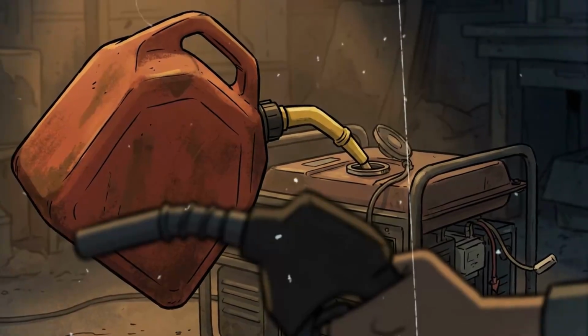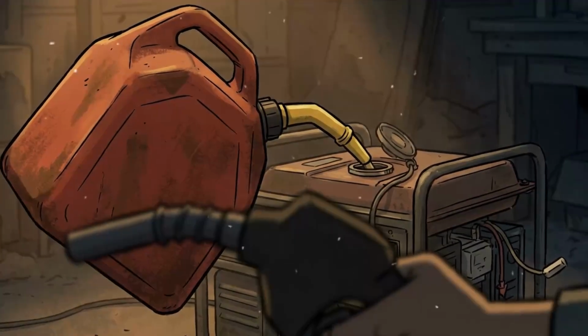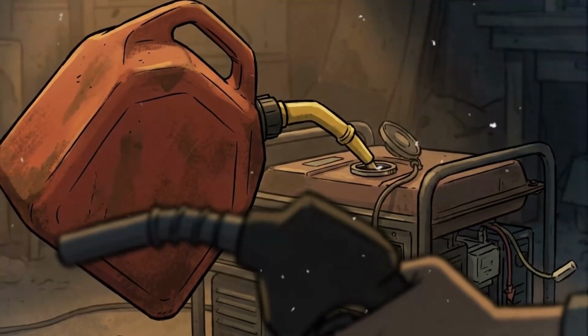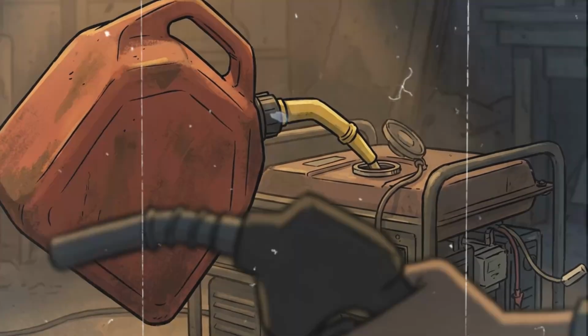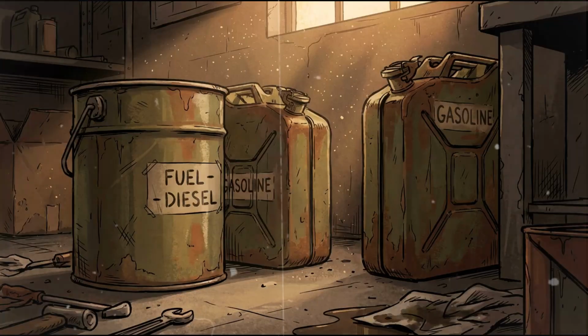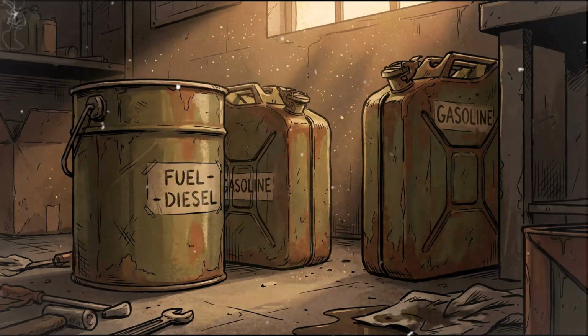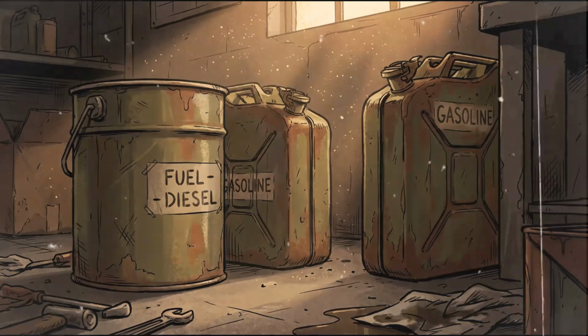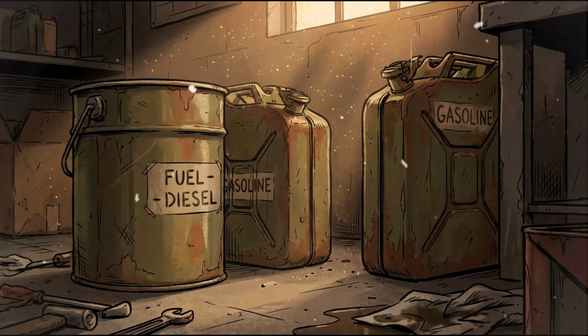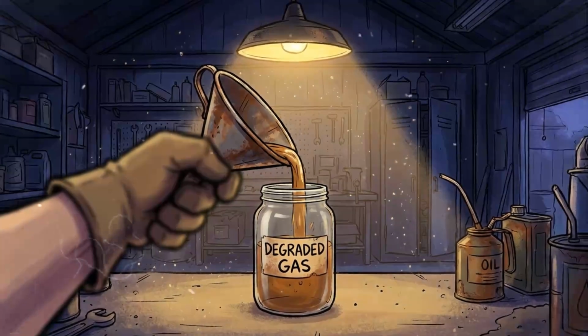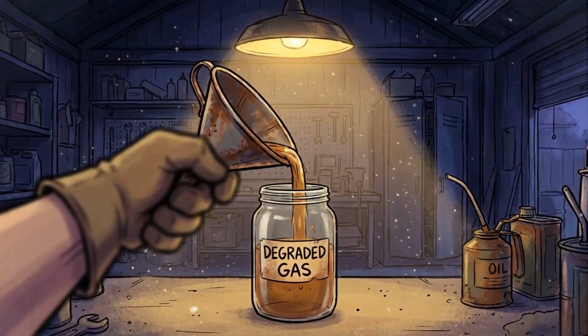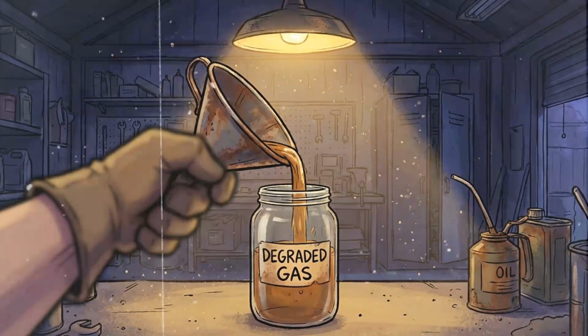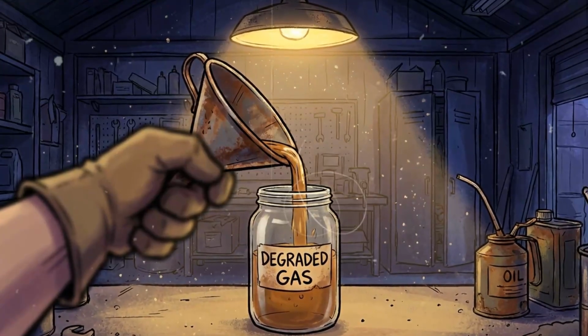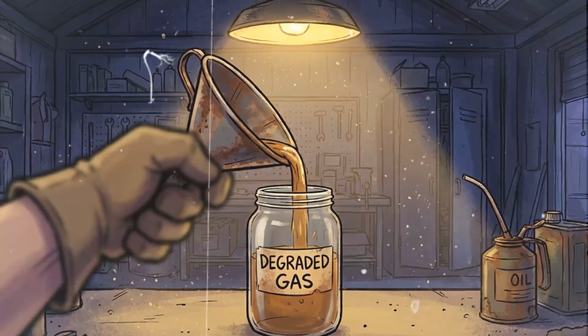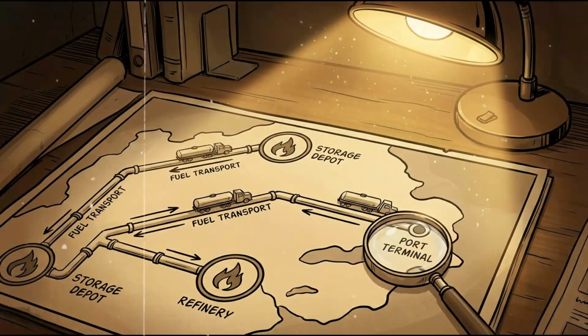This generator consumes approximately 0.6 gallons of gasoline per hour at 50% load. A 72-hour outage at moderate use, not running everything, running the essentials, requires roughly 30 to 40 gallons of fuel. The average car holds 12 to 15 gallons. You need 3 full tanks of fuel, stored and stable, before the outage to run a generator through 72 hours. Gasoline degrades. Untreated fuel stored for 6 months loses octane and starts gumming carburetors. You need fuel stabilizer, rotation schedule, and a storage system that complies with fire codes. The generator is not a device, it is a fuel logistics operation.